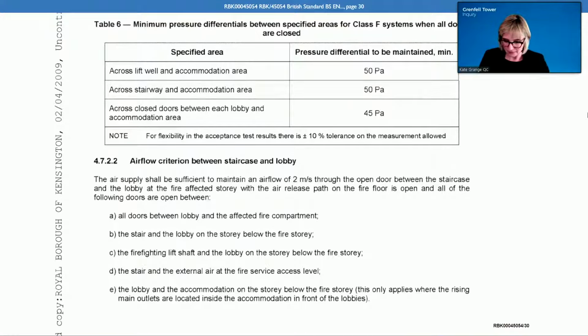You're mentioning pressure differential systems again. I'm using the SCA guide, and I believe this cited standard, the 1366 Part 2, is an acceptable standard in the SCA guide. I see. Well, we can have a look if you like. In order to be smoke control dampers, there needed to be relevant test evidence to BS EN 1366 Part 10 or classification to BS EN 13501 Part 4. You carry on, John. Sorry, and we don't have that. So the EN 1366 Part 2 for 1 hour is not enough to be a smoke control damper. Did you realise that at the time?